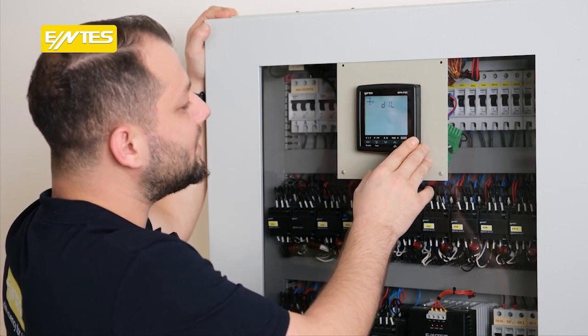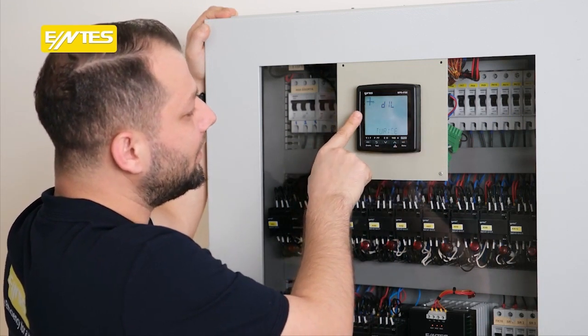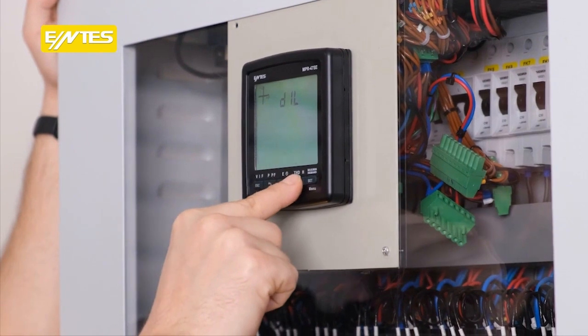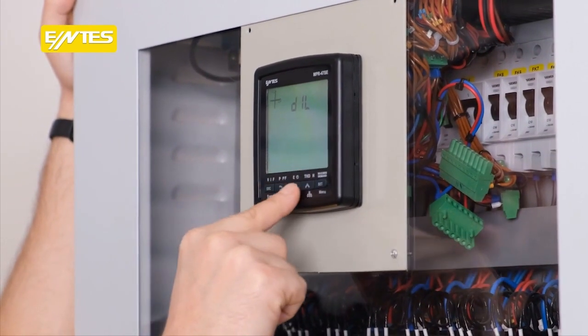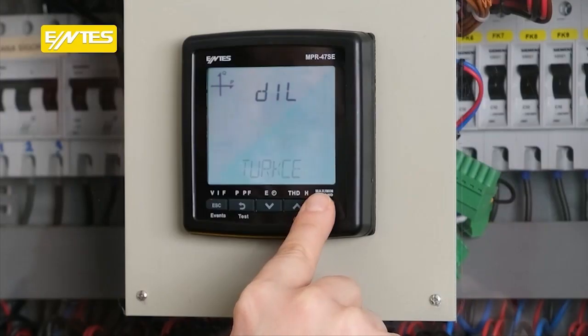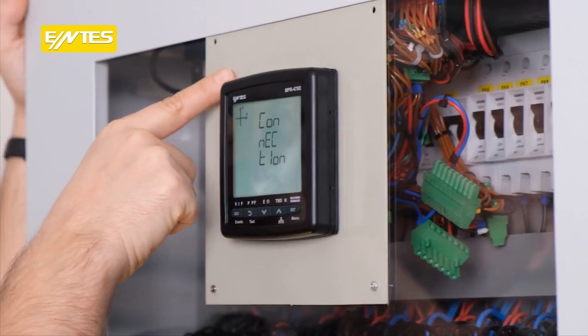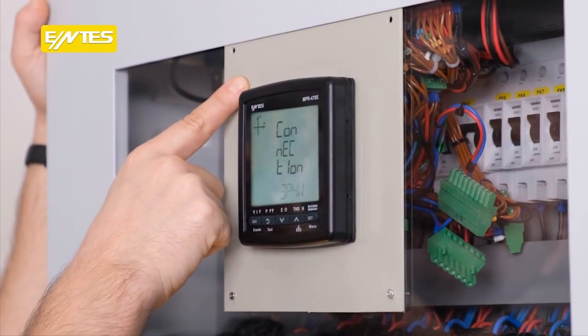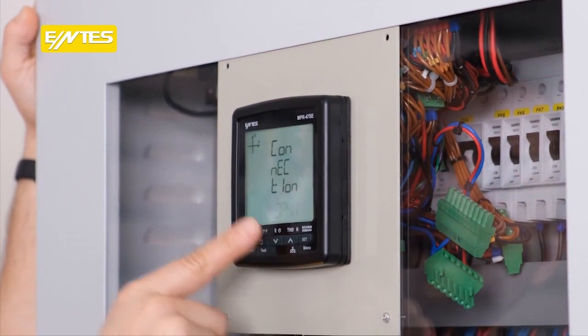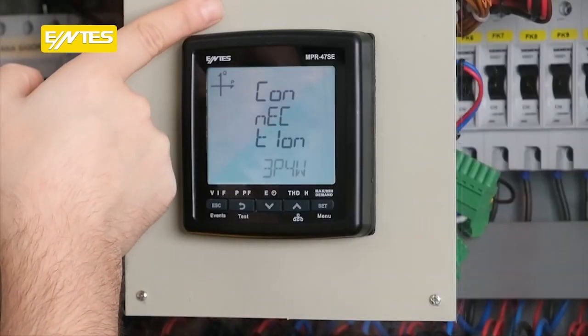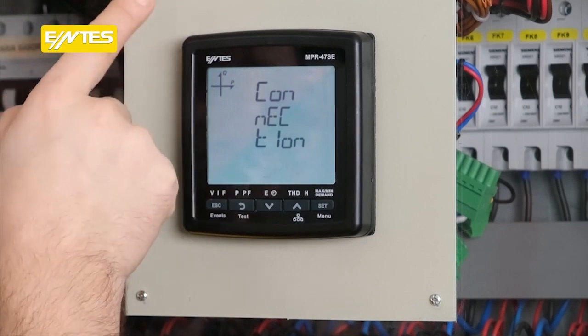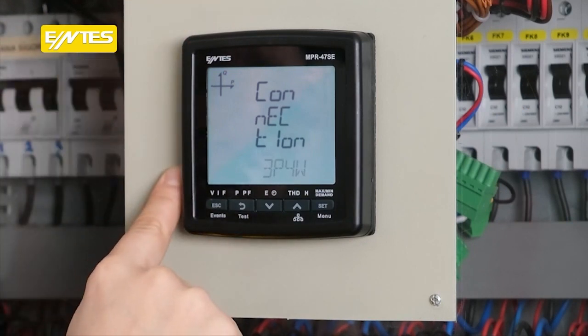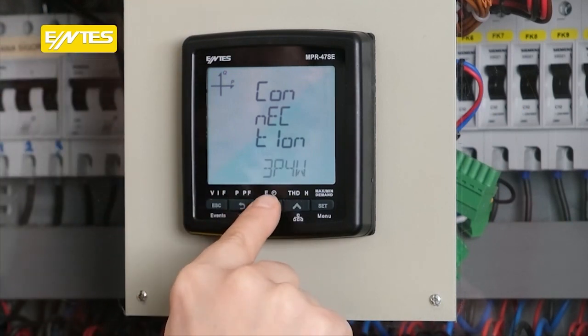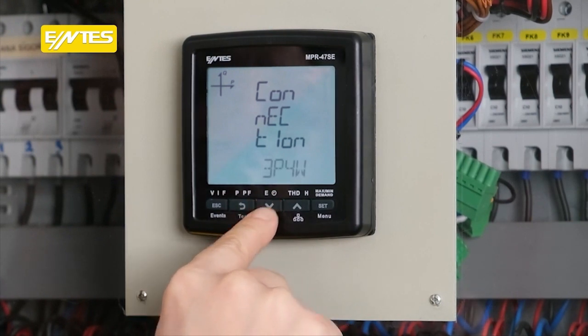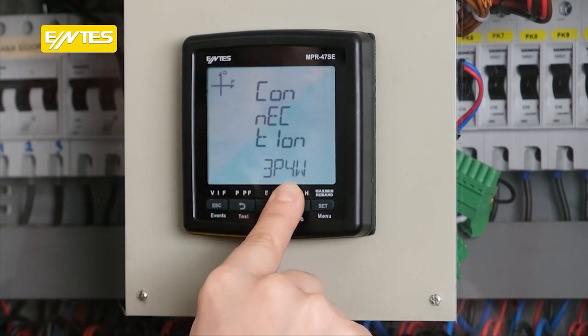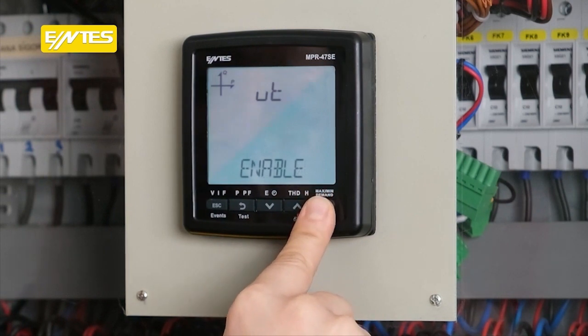We are greeted with language selection on the initial setup screen. It offers support for Turkish, German, French as well as English. We press the set button and confirm. It asks how we connect, the type of connection from the voltage measurement input on the back of the device. We connected 3 phases and 4 wires and we connected our neutral. The user manual shows the selection of other connection types. We select 3-phase and 4-wire connection. We push the set button and verify.